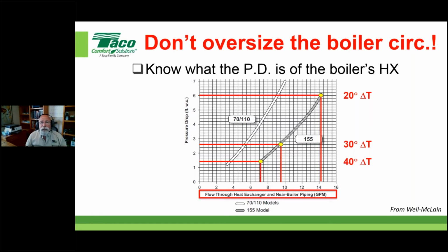I'm sticking up for these guys because when they sell you a packaged boiler, and they put a pump in there, that pump most likely is oversized. You know why? Because they have no idea what you're going to do with that assembly. They don't know what's happening on the secondary side, or if there's even going to be a secondary side, or if you're just going to use it for domestic hot water generation, et cetera. So they're just going to take a guess at what will cover them for most applications. And that's why you see the packaged boiler pumps tend to be oversized.